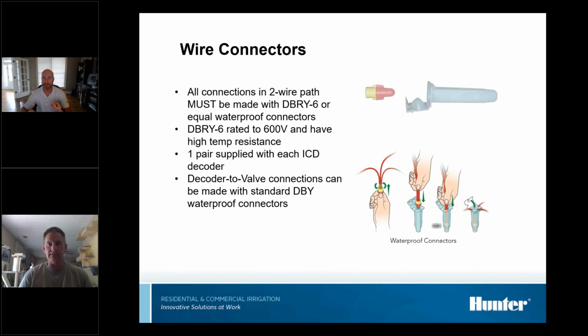Wire connectors are critical, and it's important to make a good splice. Splices in the 2-wire path, between the decoder and the 2-wire path, and any T-splice, must be made with what we call a DBRY6, a splice kit rated to 600 volts with high temperature resistance. We supply one splice kit with every decoder, so when you buy the ICD 100, you get a kit with two DBRY6s for that splice.